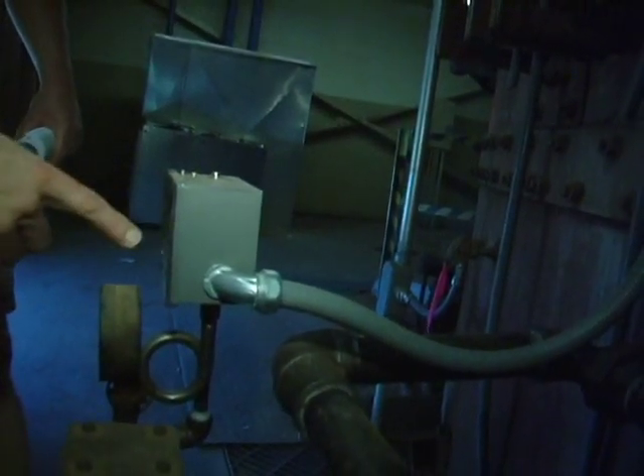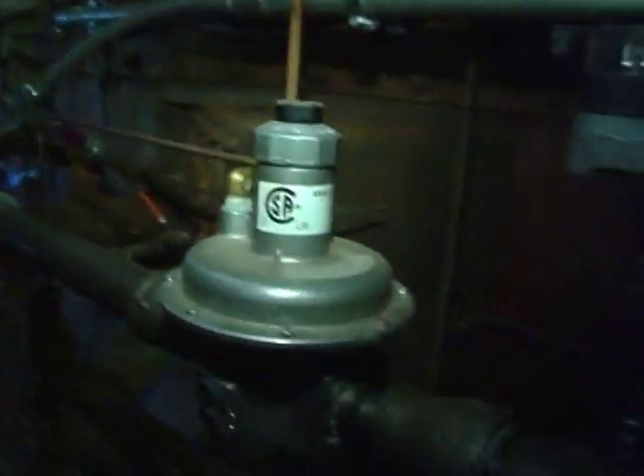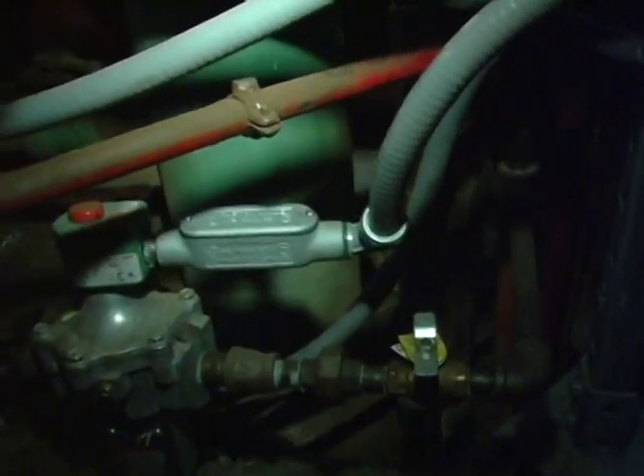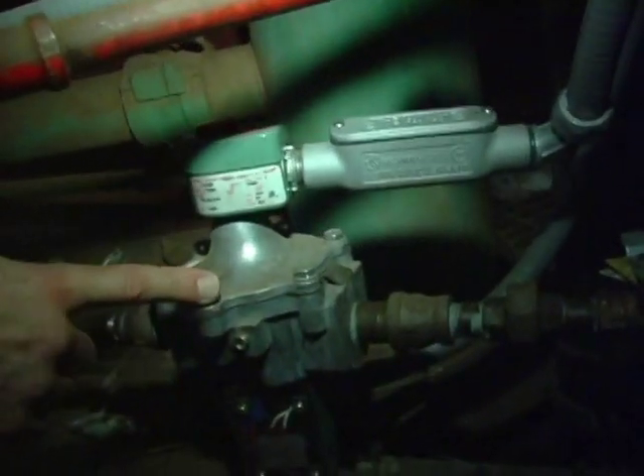You got a pressure sensor on the oil line also. There's a pressure switch there. You got to have sufficient oil pressure, okay? There's also a pilot line. There's a pilot line down here too. We go back over here, right over here, this is your pilot gas. Comes in, you got another solenoid safety shutoff valve for the pilot gas. That comes over. There's a regulator also on the pilot line, a very small regulator, and it gets vented back to the mixer there.